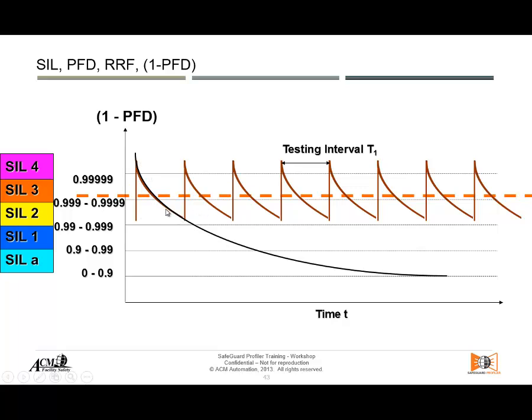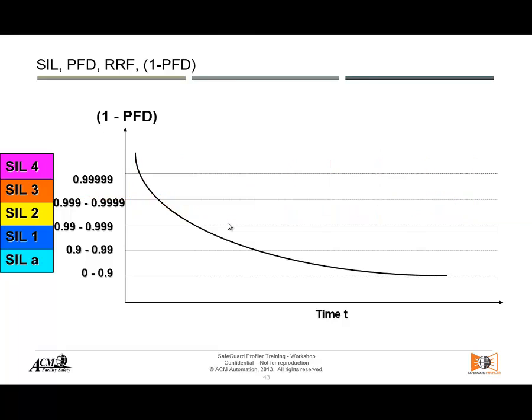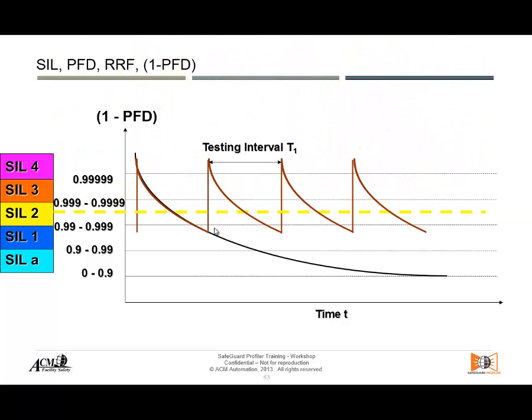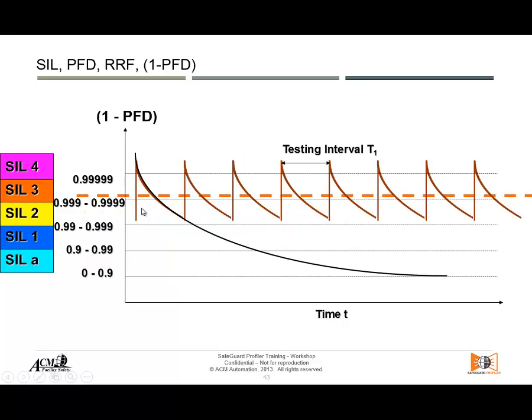As time goes by, its reliability goes down, or its probability of success goes down. And then if you proof test your equipment at that time, well, the curve starts again — you assume that it has the same reliability as when you put it there the first time, and you continue working in that way. So, as long as you're doing proof testing, what is important to notice is: if you proof test your equipment more, your reliability by proof testing more often was higher.